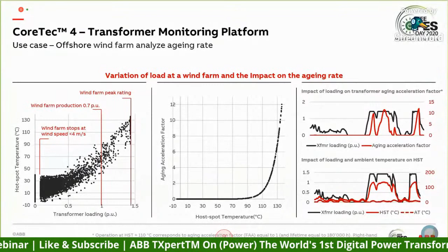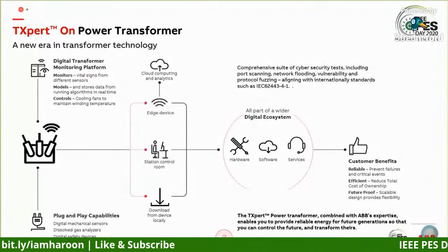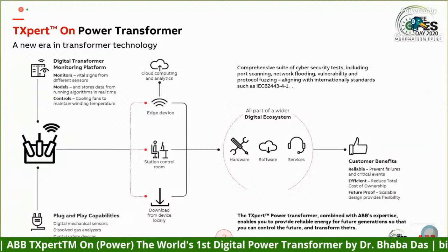So the TXpert on the power transformer gives you plug and play capabilities. You can add a lot of sensors, gas analyzers, and other safety devices, and use it as a point solution which monitors, times, models and stores data, runs algorithms, and controls your cooling fans. Then you can connect it to your station control room, where you can download the device data locally or upload it to the cloud. You can have multiple digital power transformers connected to the station room where we can do cloud computing and analytics.